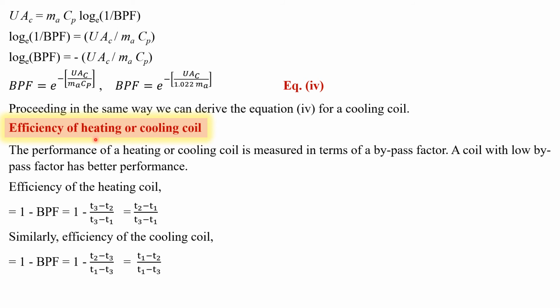Now we look at the efficiency of a heating or cooling coil. Obviously, it is clear from the preceding discussion that the greater the value of the bypass factor, the more air will not come in contact with the heating or cooling coil surface. So the performance of a heating or cooling coil is measured in terms of the bypass factor. A coil with a low value of the bypass factor has better performance. So the efficiency of the heating coil is nothing but 1 minus bypass factor. Expressing it in terms of temperature ratios, it comes out to be T2 minus T1 divided by T3 minus T1 for sensible heating, and for sensible cooling, the efficiency of the cooling coil is equal to T1 minus T2 divided by T1 minus T3.